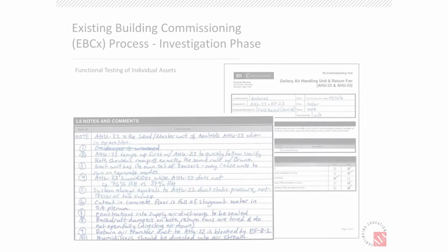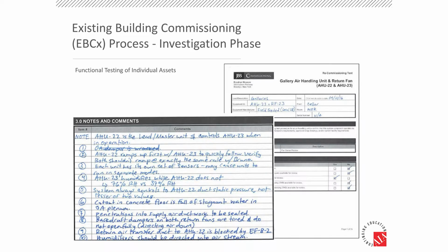We spent a lot of time testing the air handling units and the variable air volume boxes. We visited every single one with the BMS guy. And as you can see here, we found a lot of issues. Right, outside of the realm of the visual inspection, that doesn't look right, we found a lot of controls-related issues that needed to be addressed when comparing to the original design sequence of operation.